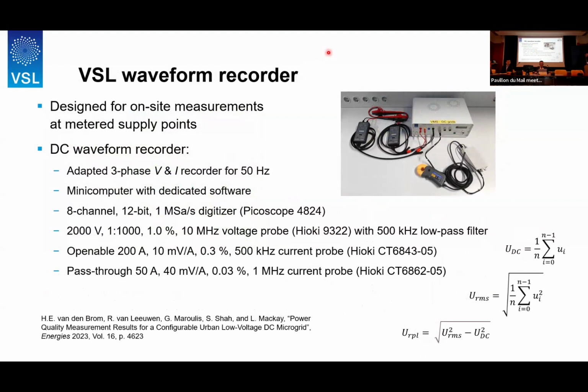So we have developed a waveform recorder for this purpose, which consists of a voltage and a current recorder, which was adapted from 50 Hertz applications to DC. It has a mini computer with dedicated measurement software, and it is based on an 8-channel 12-bit digitizer. It uses a voltage probe, which is very broadband, but we limited the bandwidth to avoid very high frequency aliasing into the bandwidth of our interest. And it had 2 current probes, which we used.